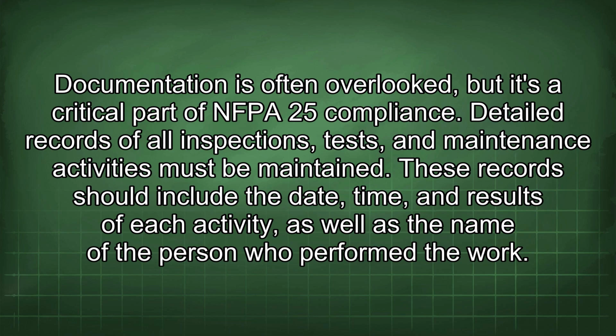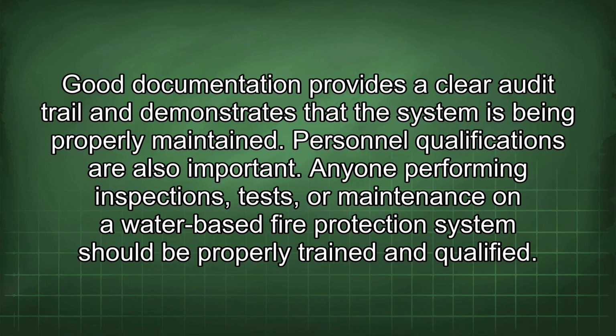Documentation is often overlooked, but it's a critical part of NFPA 25 compliance. Detailed records of all inspections, tests, and maintenance activities must be maintained. These records should include the date, time, and results of each activity, as well as the name of the person who performed the work. Good documentation provides a clear audit trail and demonstrates that the system is being properly maintained.